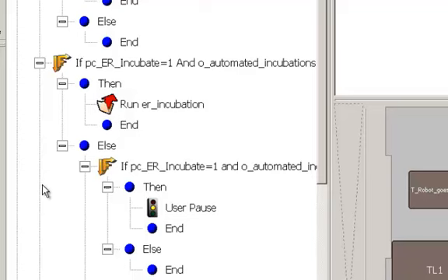But when you're adding master mixes, it all calls that one procedure, add reagents, and it uses that same procedure to add all the reagents, whether we're adding the end repair, the ligase. And when you're doing the AMPure, it calls that one AMPure procedure. We can change the elution volume in that AMPure procedure. We can change the sample volume going into that AMPure procedure, but it all calls the same AMPure procedure.